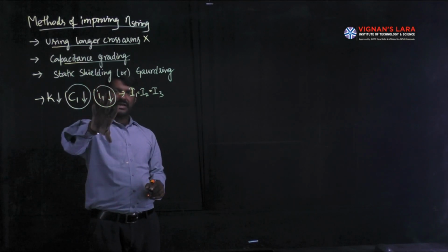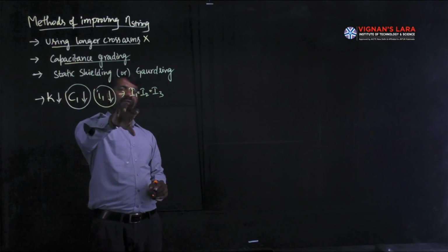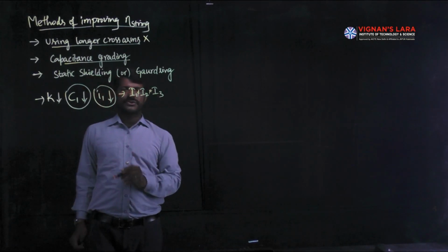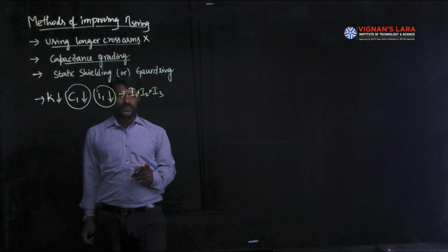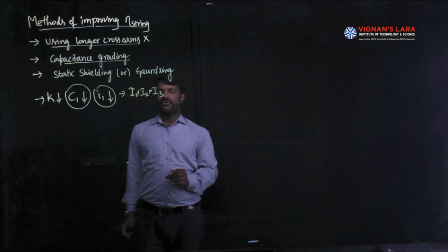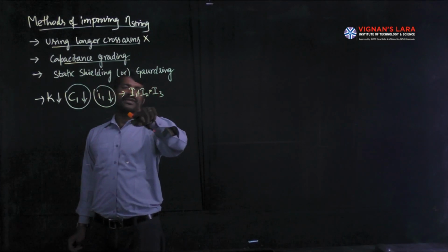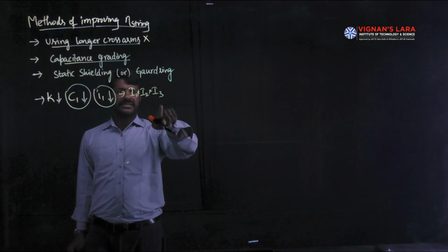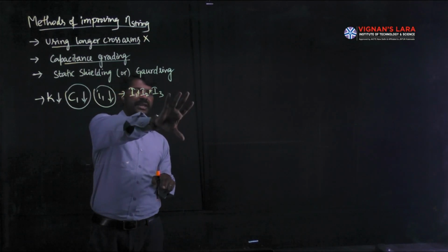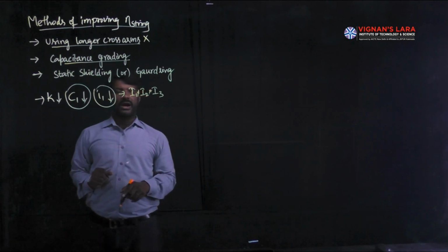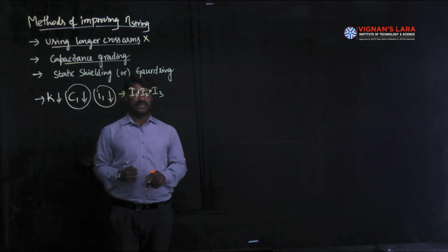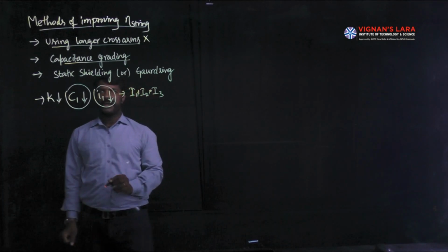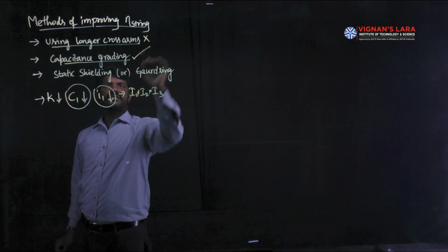With this shunt current I1 and with unequal currents I1, I2 and I3, whose magnitudes in general will be I1 less than I2 less than I3, for such unequal currents in the shunt branches, the voltages can still be achieved equally among all three units. In our example there are three units, by grading the capacitance using this second method.